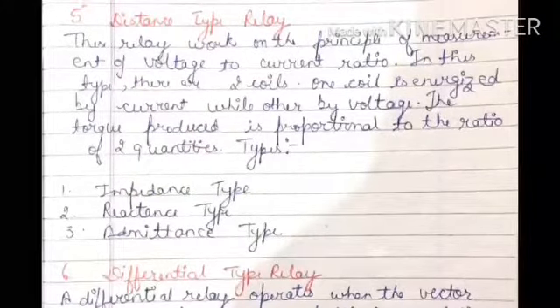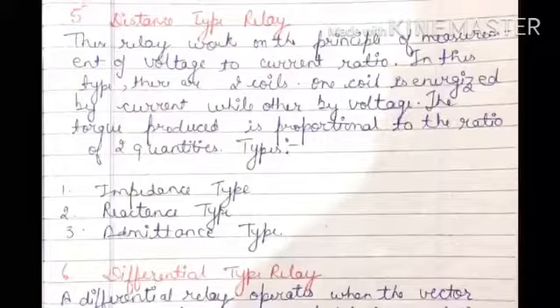Then we have the distance type relay. This relay works on the principle of measurement of the voltage to current ratio. There are two coils: one coil is energized by the current and the other coil is energized by the voltage. The torque produced is proportional to the ratio of these two quantities. When the ratio reduces below a set value, the relay operates.